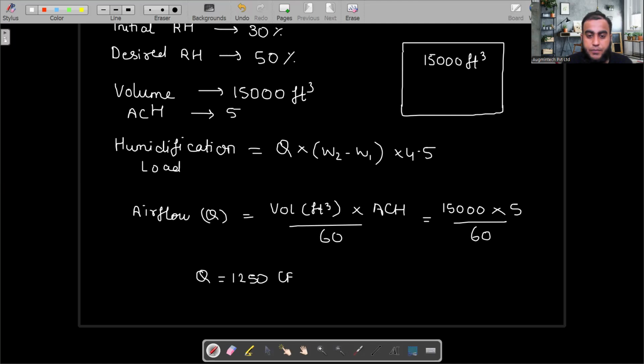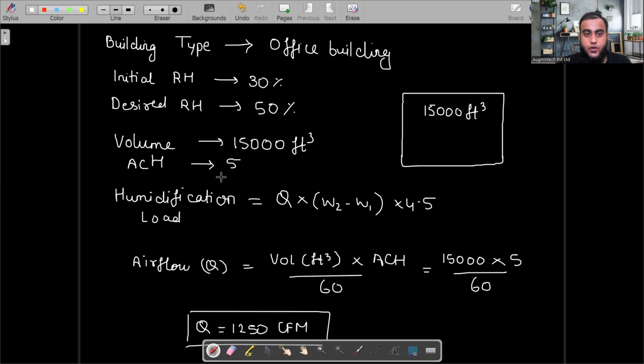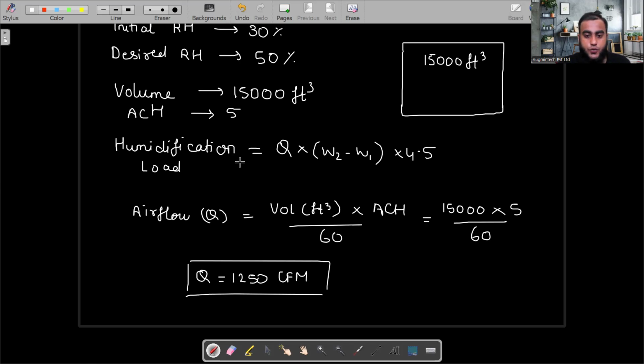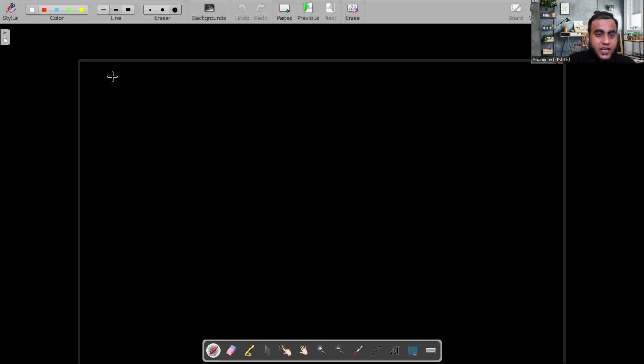The unit is cubic feet per minute, CFM I have written. Next, the values which we need are W2 and W1, meaning humidity ratio values. Based on your initial relative humidity, you have to calculate the humidity ratio value, and based on your desired relative humidity, calculate the humidity ratio value. So I'm opening the next page. First, what is our initial relative humidity? 30%.